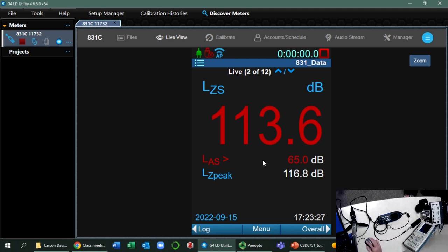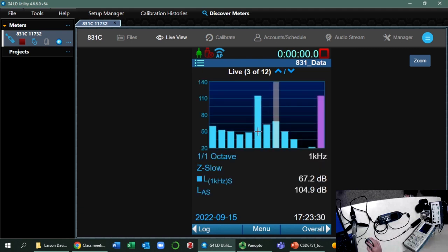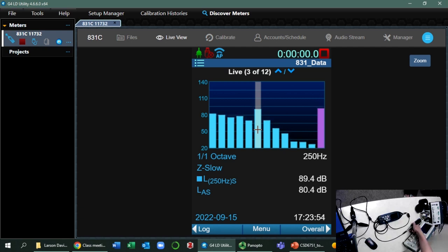It's close, but we should look at this and select 250 Hertz. This is the correct way to calibrate the sound level meter using an acoustic calibrator, because we are concerned about the frequency specific accuracy. We don't worry about other frequencies because this calibrator produces only 250 Hertz. Does that make sense? So we look at the frequency specific.